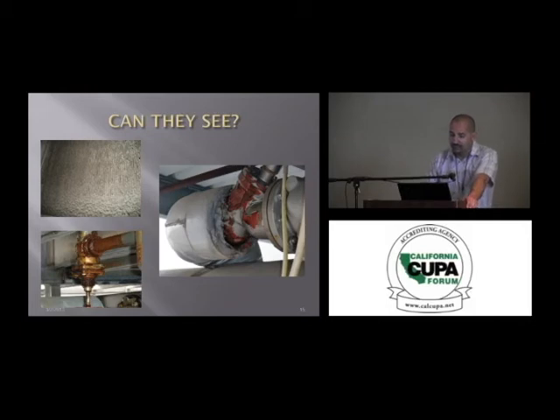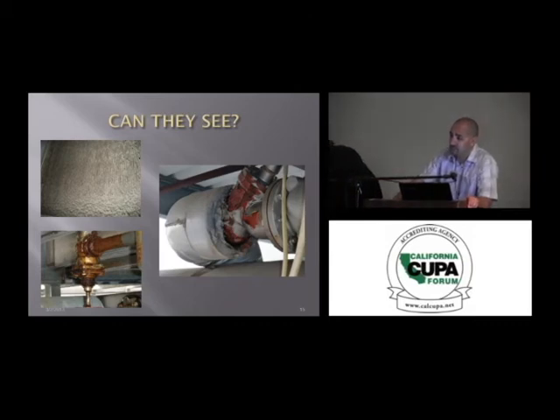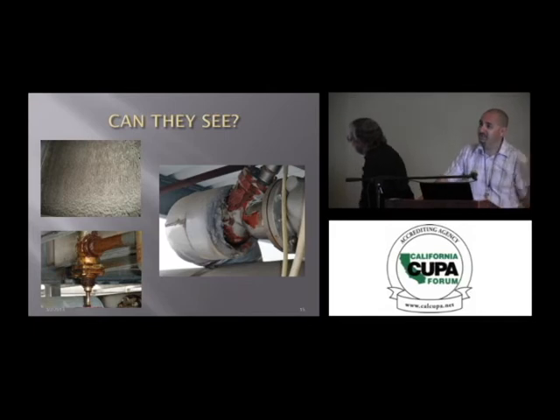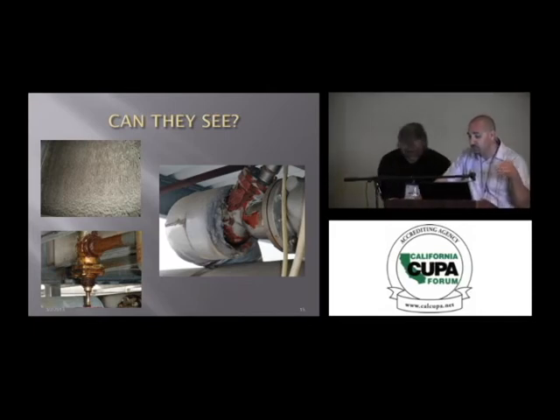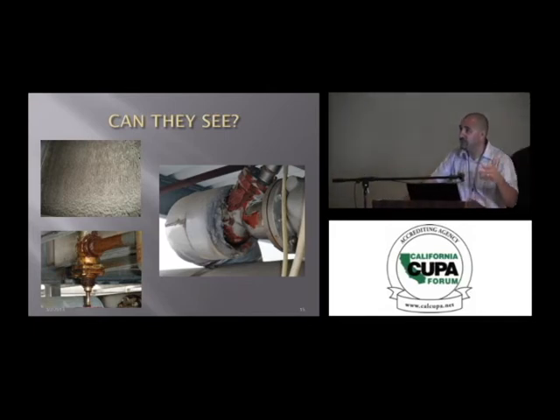Top left-hand side. What is that? Who knows what piece of equipment that might be? That is a plate fin ceiling suspended coil. What cools down the air that flows through the coil is the fins, where the cooling process is going on. This, it's just dirt buildup. It's a wall of dirt buildup, and there's no refrigeration going on through that coil.